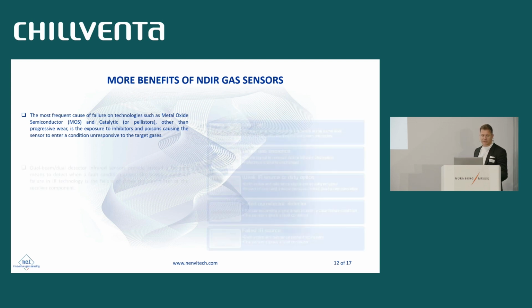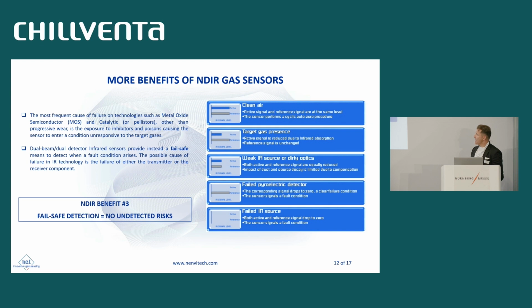Another important aspect is that the sensor is what is called fail-safe. What do you mean by fail-safe? We mentioned that before. The sensor will always inform you if there's a condition where the sensor becomes unresponsive to the gas. In clean air with the sensor functioning, both active and reference are at the high level, and that means no gas in the environment. When there is a presence of gas, the active signal is attenuated while the reference remains intact. That means we have presence of the gas and we measure the corresponding concentration.